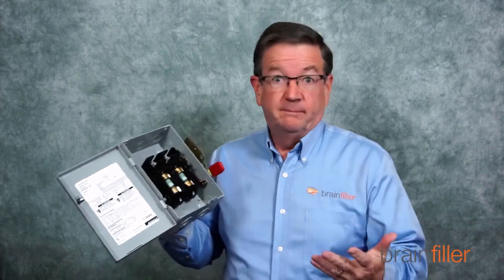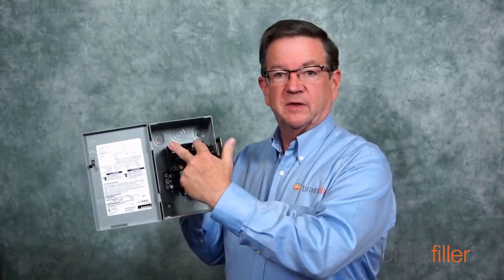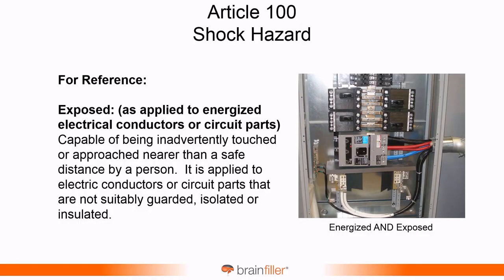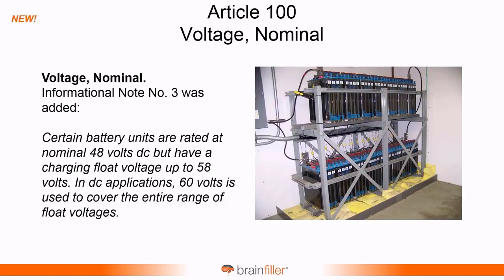That's still not a hazard. Actually, it would be. Of course, this isn't wired into anything, but if this was connected, there'd still be a hazard up here at the top terminals. So this was a bit of a clarification that it's not just energized conductors, it's exposed energized conductors. Part of this is that there's a definition within NFPA 70E for the word exposed. This definition has already been there, and it's for conductors and circuit parts capable of being inadvertently, that's a key word there, touched or approached nearer than a safe distance. So this definition is there, and the word exposed has been added to the shock hazard.